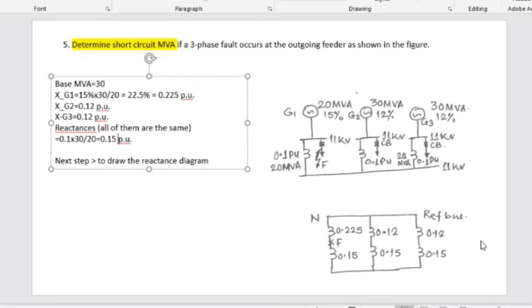Please confirm that you understood how the reactance diagram is drawn, because that is where the trick is. Calculation of reactances you can do — after doing four or five tutorials, you will be able to calculate reactances for each generator, reactor, line resistance, and line reactance. But when it comes to the reactance diagram, that is where we might start making mistakes. We cannot afford to make any mistake: the fault currents will be wrong, the fault MVA will be wrong, all those currents will be wrong, and we'll be putting in wrong relays and wrong settings — everything will be getting damaged in no time.